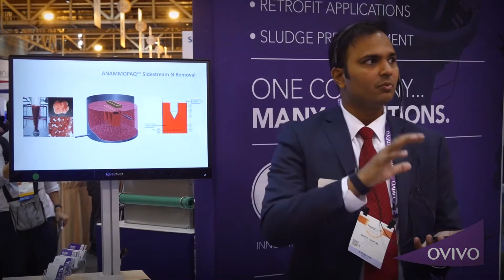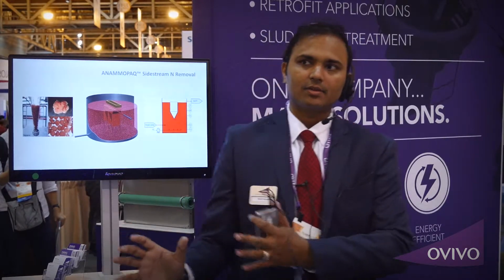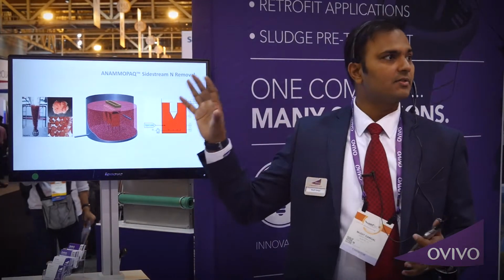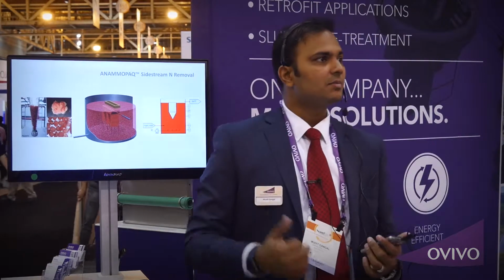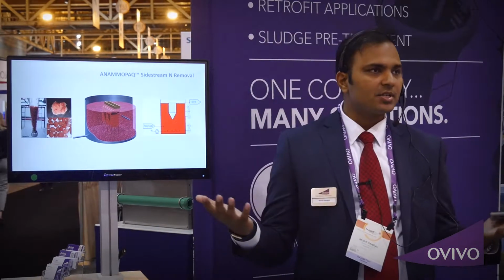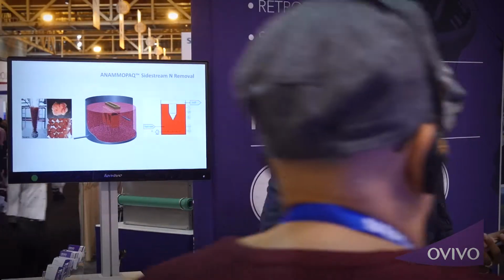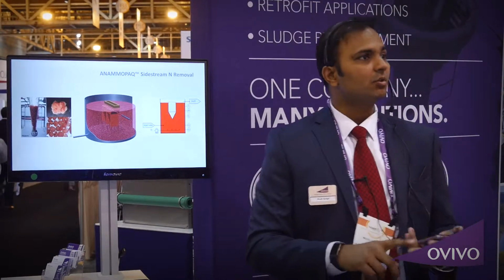So that was on the digestion side, but now we look at the opportunities. Now looking at the challenges side also with anaerobic digestion is the production of side streams. And these side streams can be very high in ammonia. They're about 1% of the flow, but you're looking at 30-40% of the load of the main treatment plant because of this. So either nitrogen or phosphorus, which could be addressed by using Anammox bacteria.